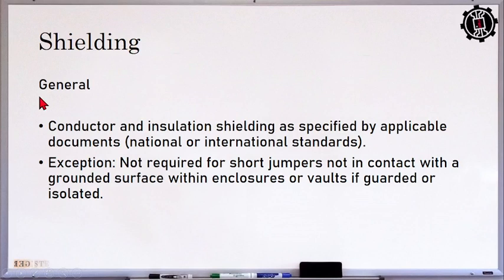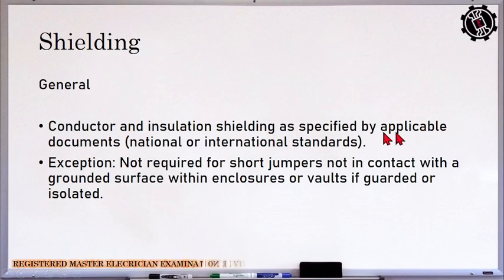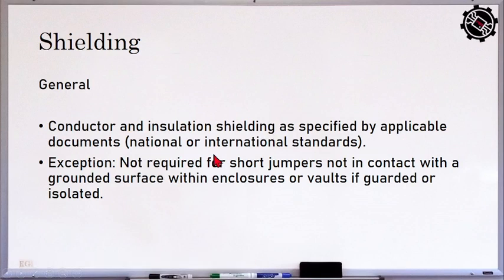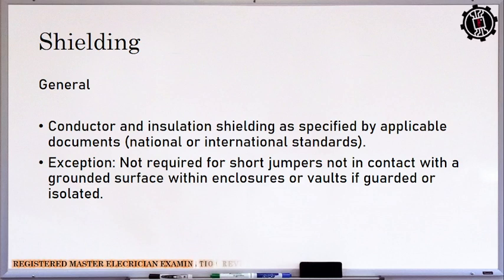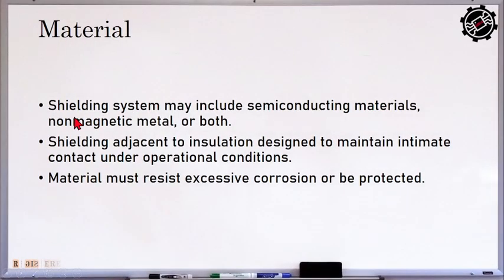So shielding. In general, shielding must be the conductor and insulation shielding as specified by applicable documents. So anong mga accepted na materials to be used for shielding sa ating cable. It is not required for short jumpers not in contact with a grounded surface within the enclosure or vaults if guarded or isolated. The shielding system may include semiconductor materials, non-magnetic materials, or both. The shielding adjacent to insulation is designed to maintain intimate contact under the operating conditions. Then materials must resist excessive corrosion or must be protected from corrosion.